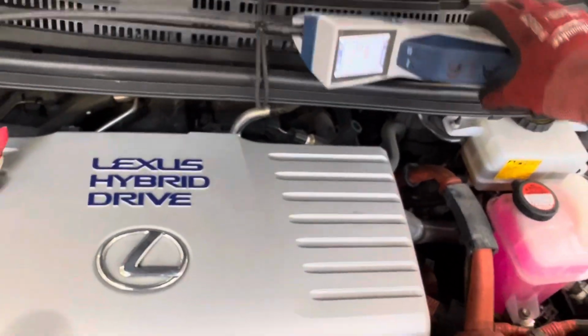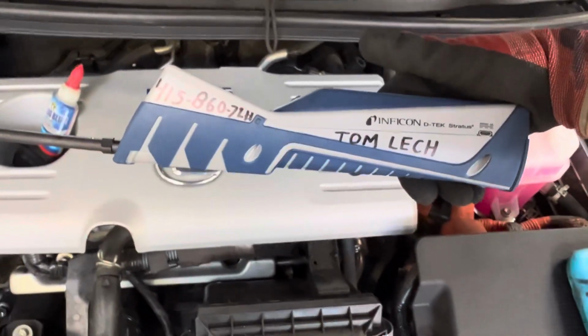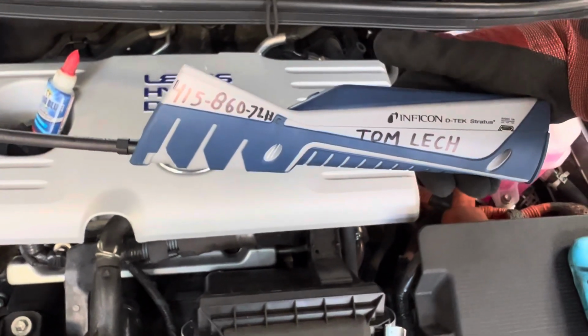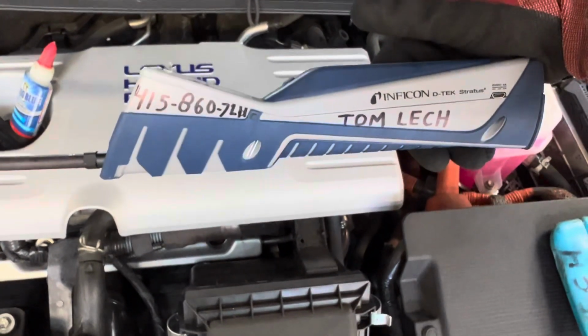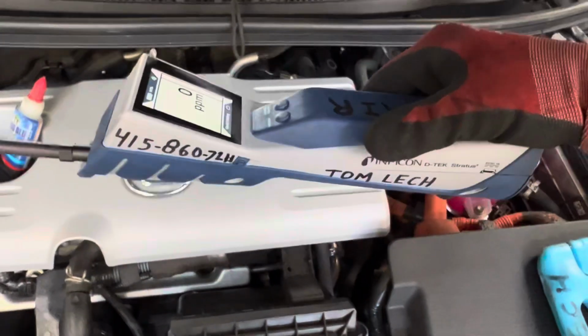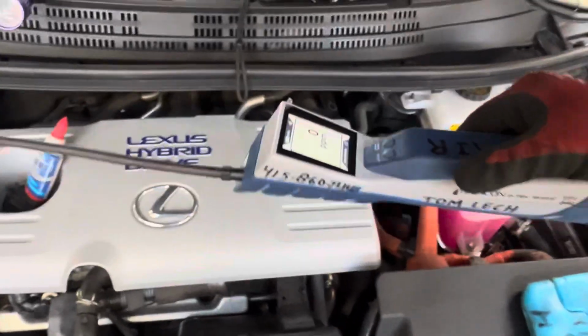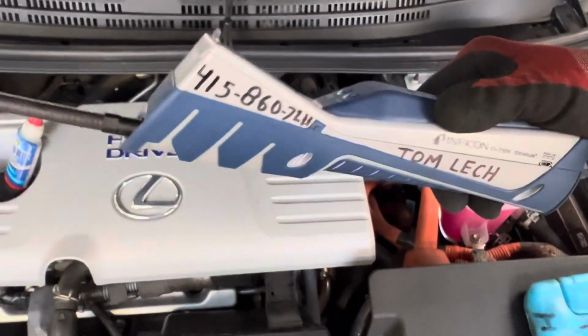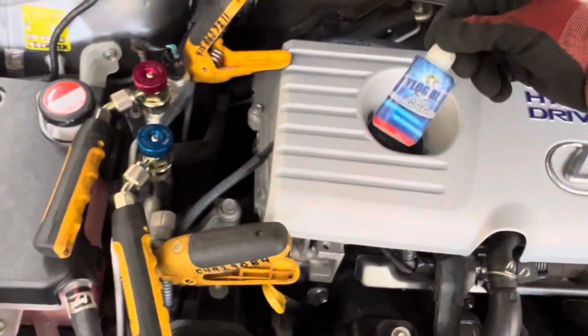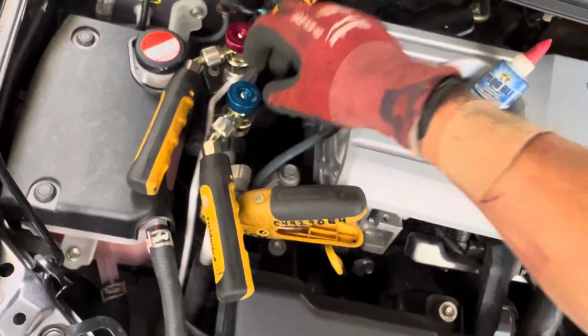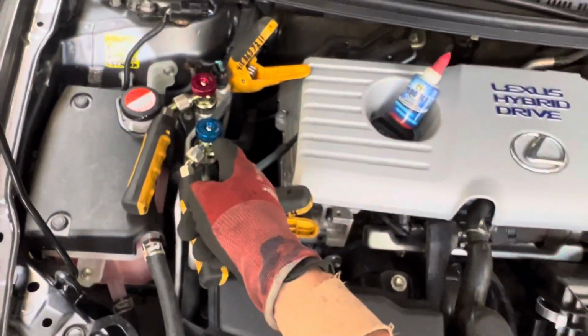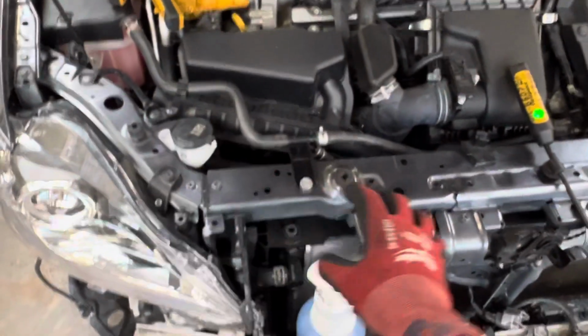Remember the best leak detector. The other one is the H10. You could go down, but the Inficon D-Tek Stratus is really sensitive and really good on the YF refrigerant. And don't forget to use your Nylog on all your seals, especially when you are attaching your couplings, so you protect your O-rings and don't have vacuum leaks.